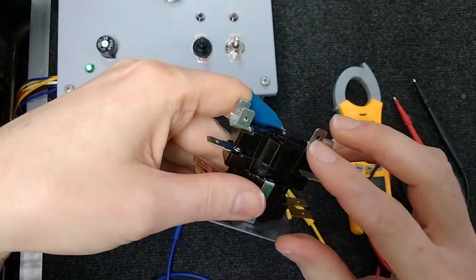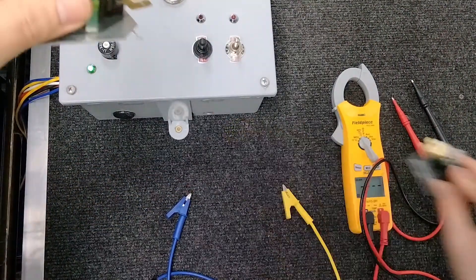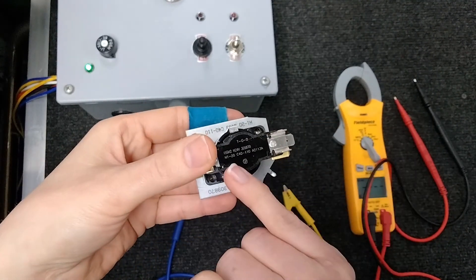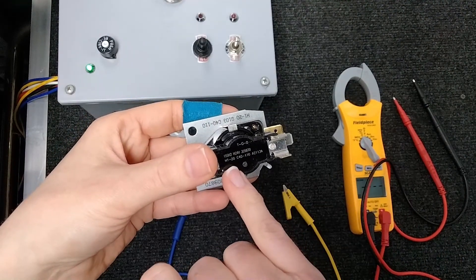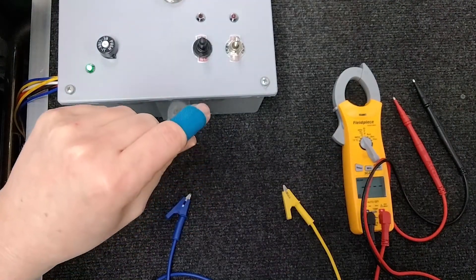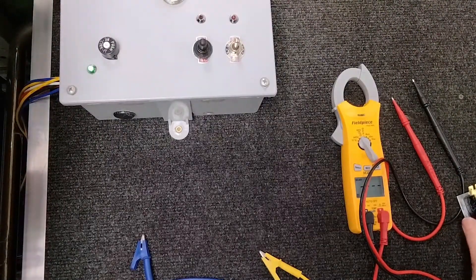Some of you may even have a three-stack. Whether you have a single stack, a double stack, or a triple stack, they're all going to be connected to the same timing. Whether it's a single, a double, or a triple, they're all going to close the circuit with the same delay. Keep that in mind when you're checking it. I have noticed with some three-stacks there is just a nanosecond difference, but they should all open very, very similarly at the same time.